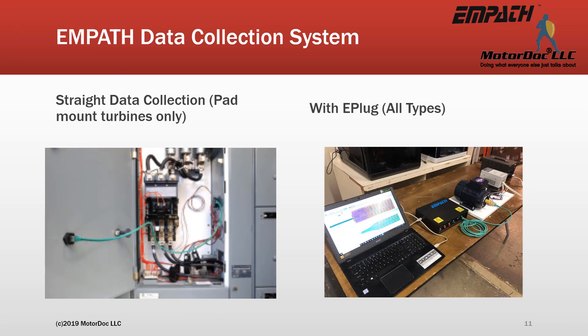When the transformer is located in the nacelle, such as with Vestas designs, an E-plug is vital. The CTs are installed and voltage is connected at the point between the controls and stator. A CAT-5E cable is used to drop the data to the base of the tower, where the data collector and laptop are used to obtain the data. The results will be the same.